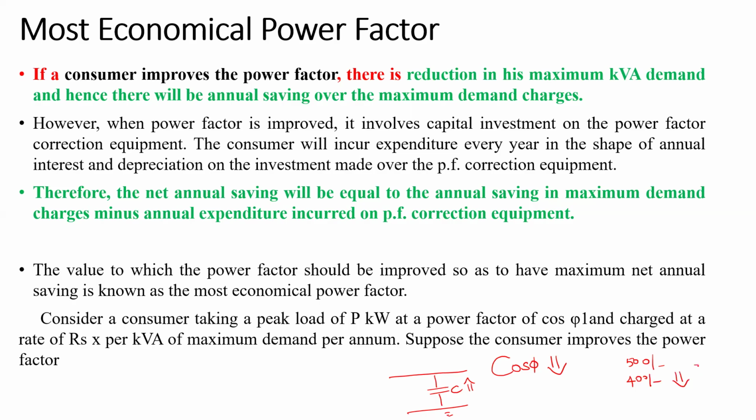How much is the savings now? 100. But you have to consider one more thing here. We reduce the bill by 100 rupees by placing one capacitor, but please consider the charge of this particular capacitor also. The cost of installing this capacitor may be 50 rupees. What's the net saving now? Only 50 rupees is the final saving. Consider that also for the annual or net saving.